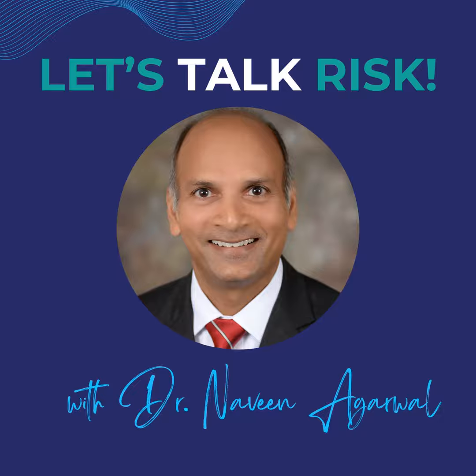But it's really important to frame the risk accurately. Boston Scientific's own analysis, their internal numbers, estimated the actual reported global rate of air embolism was quite low. How low? Around 0.06% of procedures, which sounds tiny. It does. But, and this is the crucial part, the associated death rate, while even rarer, was estimated at about 0.0009% of cases. And that's the classic QARA nightmare, isn't it? Low frequency, but incredibly high severity. Even a handful of tragic outcomes triggers a massive response. Exactly. That's the Class 1 trigger.